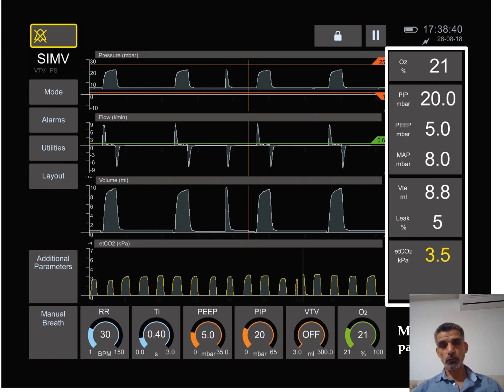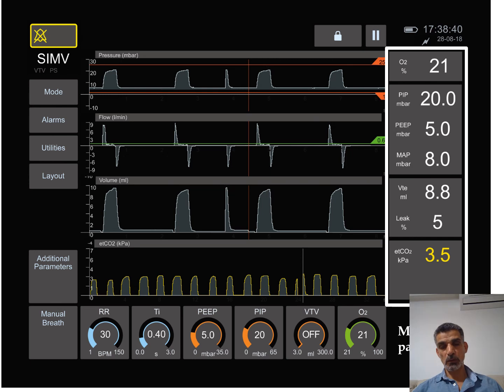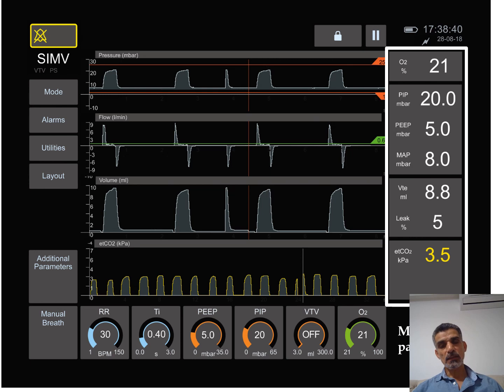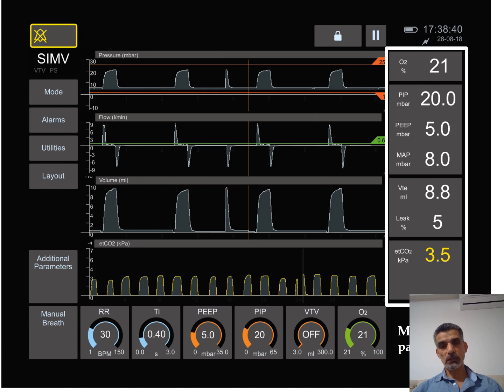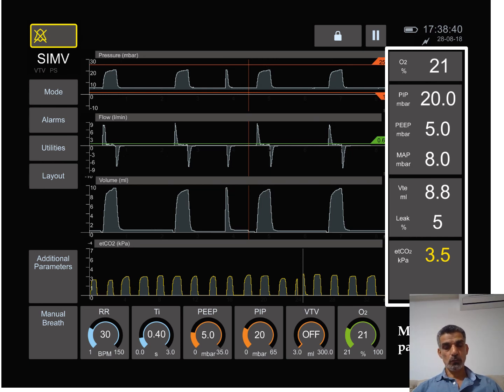This is the measured tidal volume. We can set it from here but sometimes we don't. It's measured here. Also this tells us how much leak. The leak is how much pressure is leaking around the tube. The ventilator measures the leak by measuring the difference between the in and the out. It also measures pulmonary mechanics and tells us the compliance and resistance.